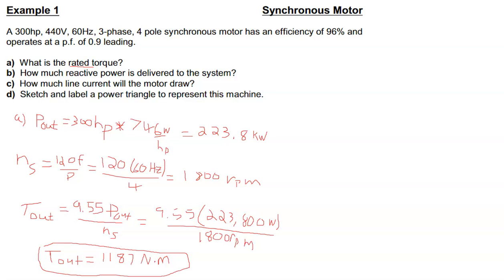Okay, now part B. How much reactive power is delivered to the system? How do you know reactive power is delivered to the system? Normally a motor draws reactive power from the system. Here we're told that the power factor is leading. And so that means the motor is overexcited, is acting like a capacitive load instead of an inductive load, which means that it delivers reactive power back to the system.